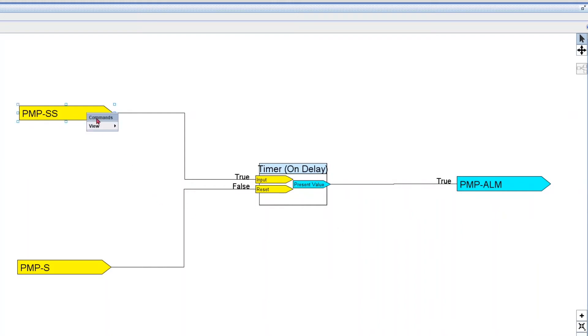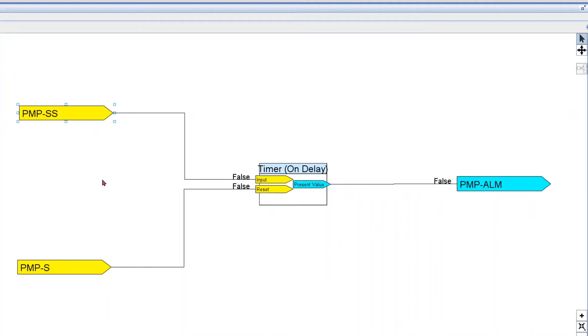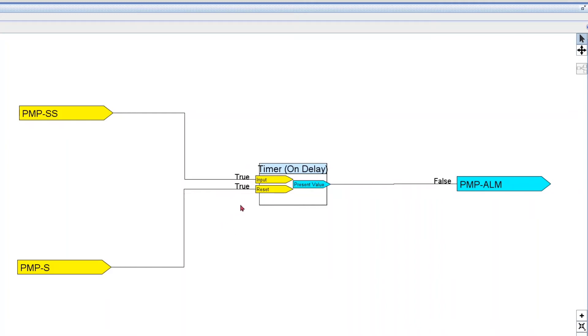Let's try it one more time. Let me stop my pump — let's say we want to stop it. False, no alarm, false. Now I'm gonna give it a start command and the timer is gonna start again. We have 15 seconds to get a pump status, so if I give a true to my status within those 15 seconds, we're not gonna get the alarm. The alarm remains false because we gave it a start command and the pump takes a couple seconds to start — it started and no alarm was activated. We always want to give it some time.